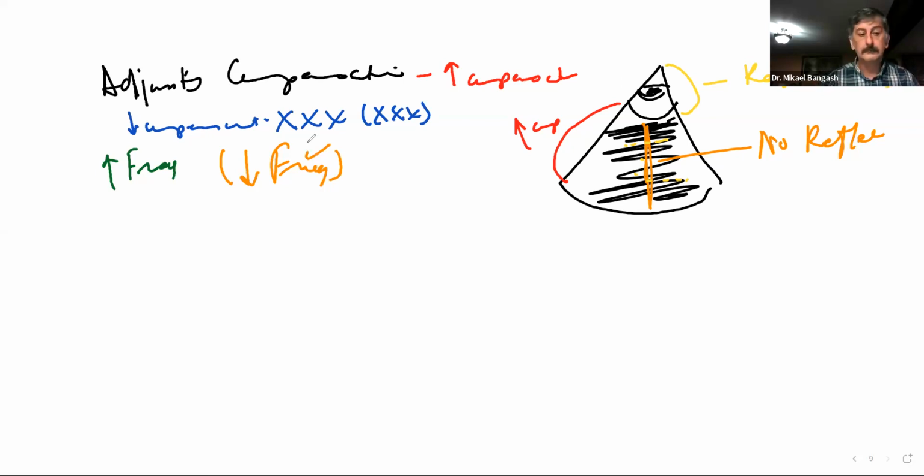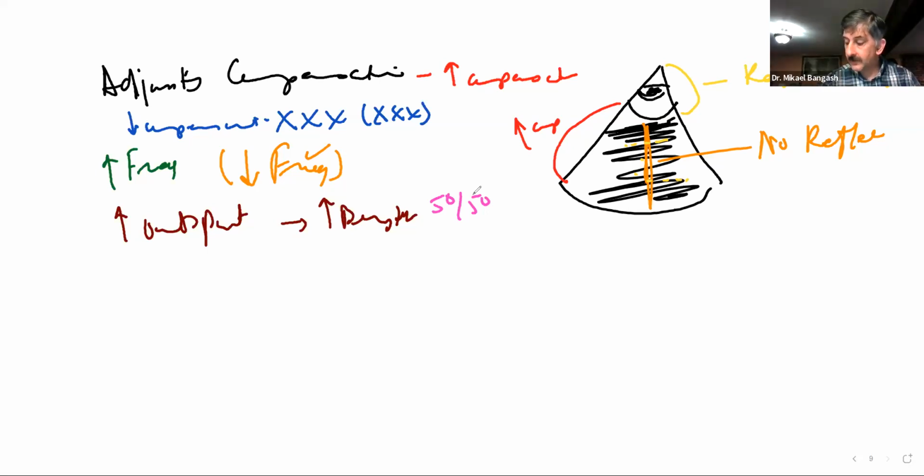Increase the output power. Now, that can make the image brighter. But that's not the solution here, mainly because there's still some part of the image where we have some reflections. So this one here is a 50-50. Adjust the reject level. Well, that's completely out of the question because we have no noise.